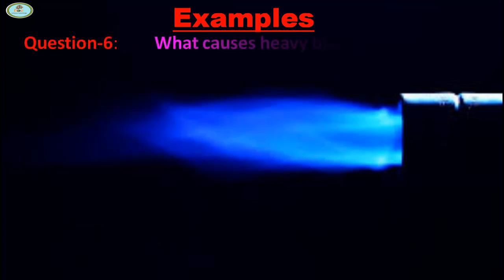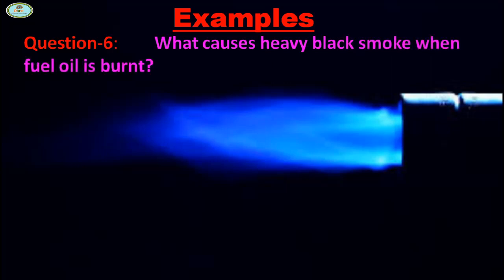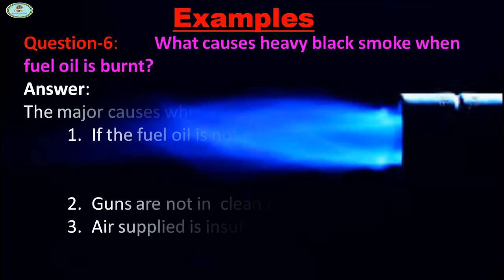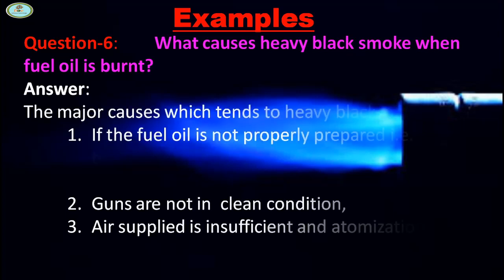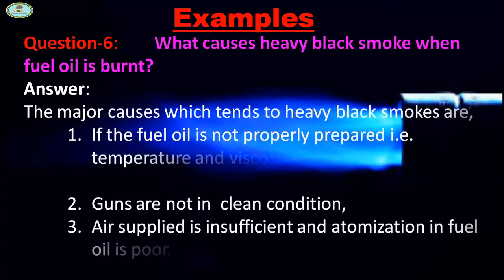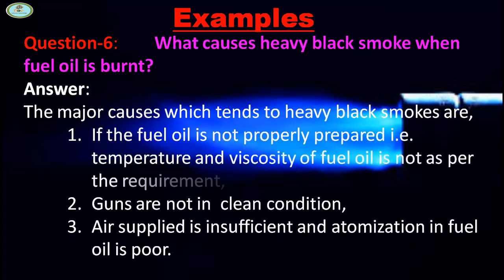Next is: what causes heavy black smoke when fuel oil is burned? The major causes which tend to produce heavy black smoke are: if the fuel oil is not properly prepared, the temperature and viscosity of fuel oil is not as per requirement.